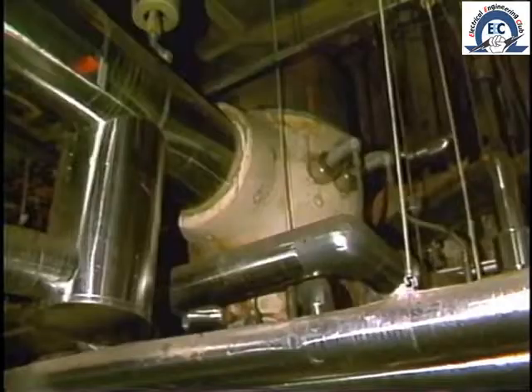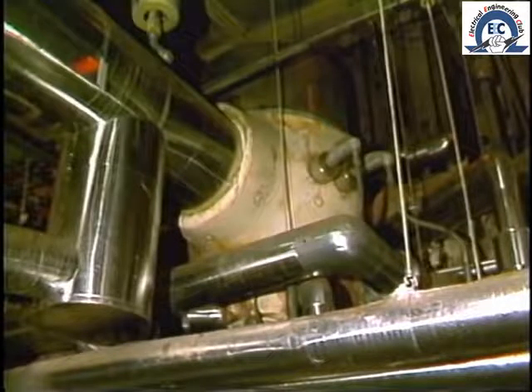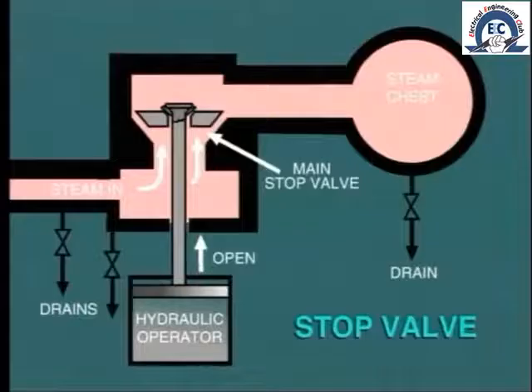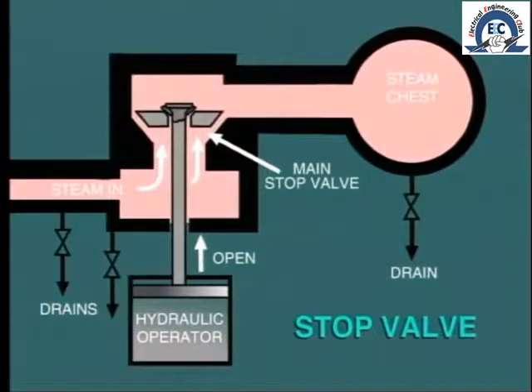An extremely important test maneuver is the exercising of the turbine stop valves. The test circuit allows the stop valve to partially close and then open again. This test is performed daily in many plants, and the objective is to make sure that the stop valve does actually move and not remain frozen in the open position, as has actually occurred on some occasions. All of the protection devices in the world are of no use whatsoever if the stop valve failed to close when commanded.